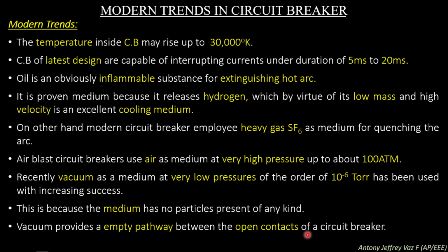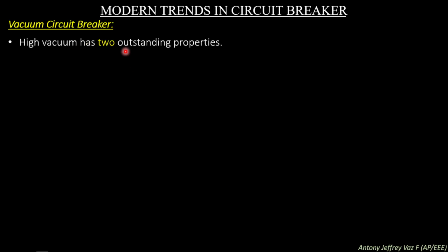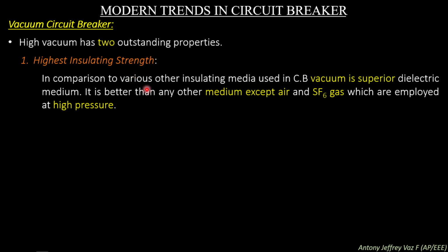So the medium in which the arc is produced is not present. The vacuum circuit breaker is used to extinguish the arc at an easier rate when compared with any other type of circuit breaker. High vacuum has two outstanding properties. It has a very high insulating strength in comparison to the various other insulating media used in circuit breakers. Vacuum is a superior dielectric medium. So when compared with air, air blast, oil or any other circuit breaker, vacuum is a superior medium and has a very high dielectric strength.